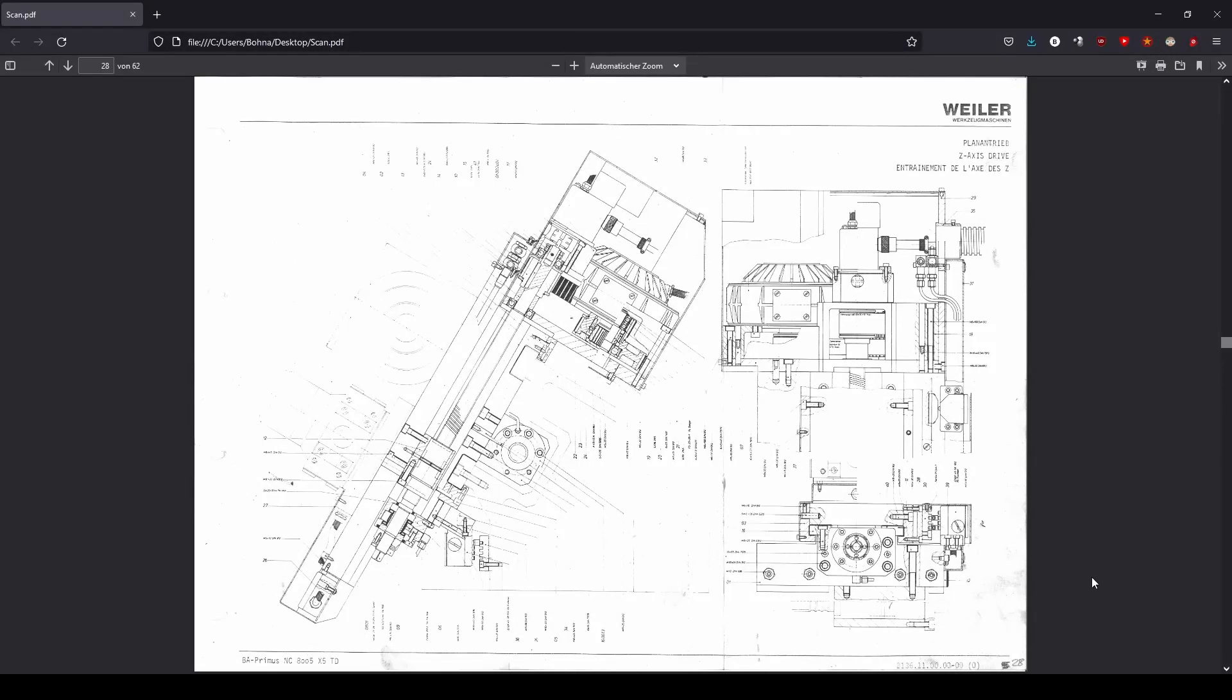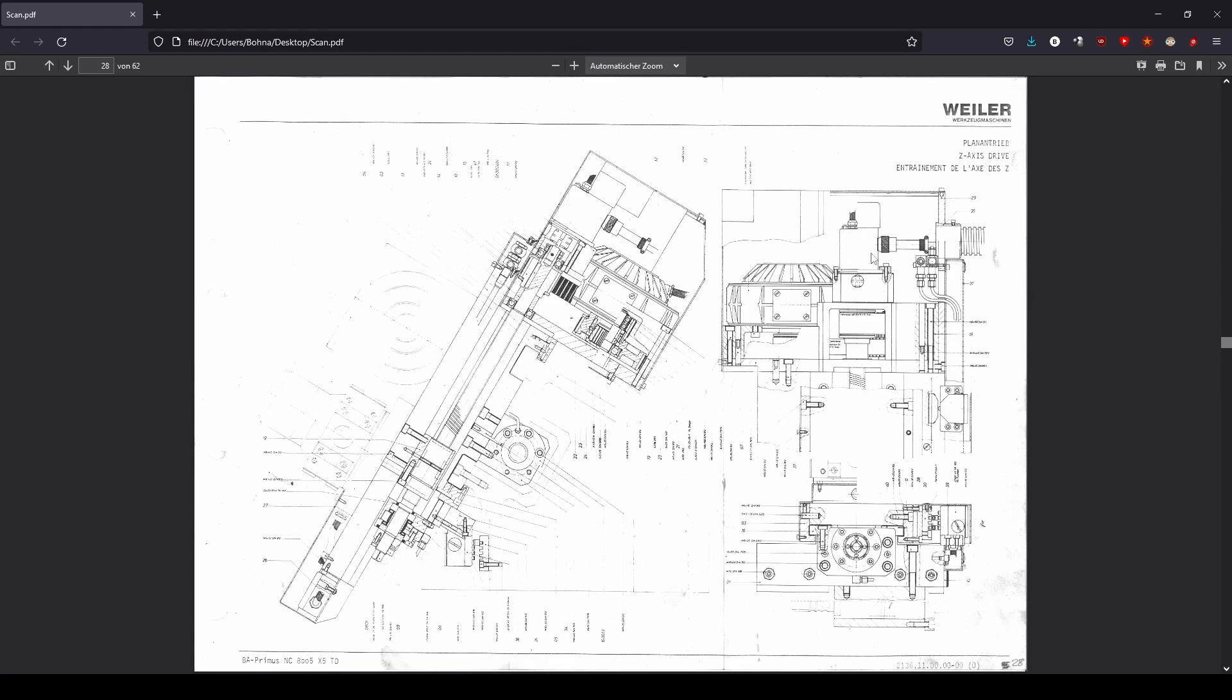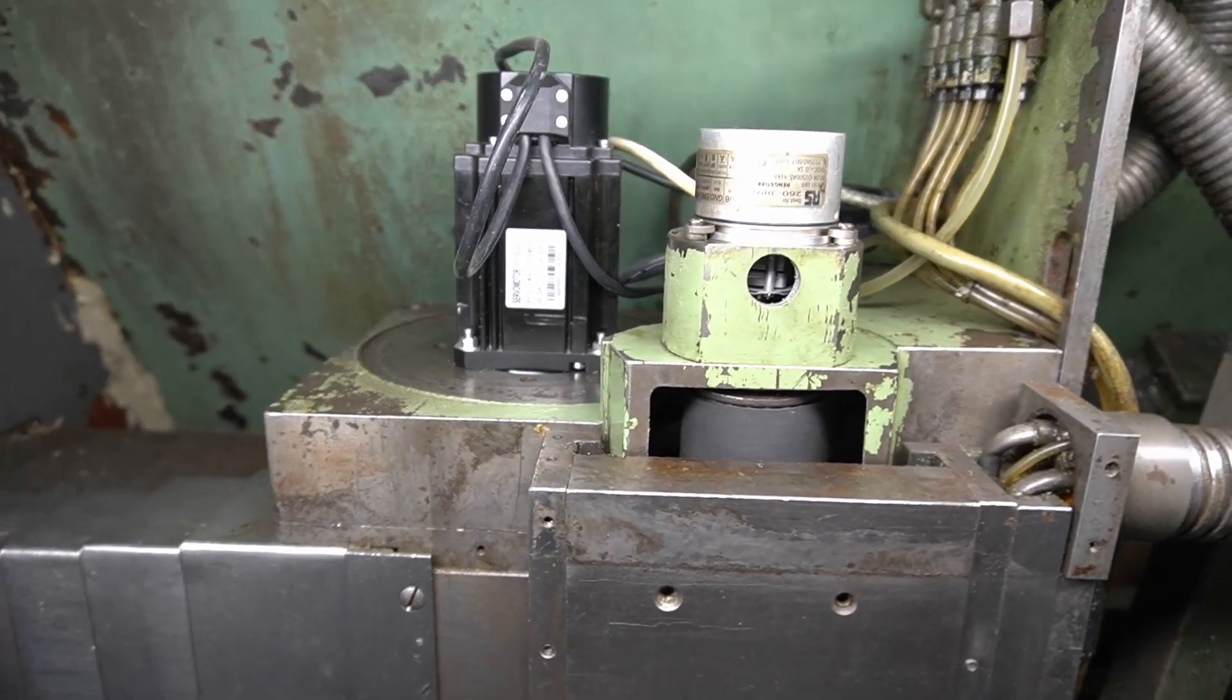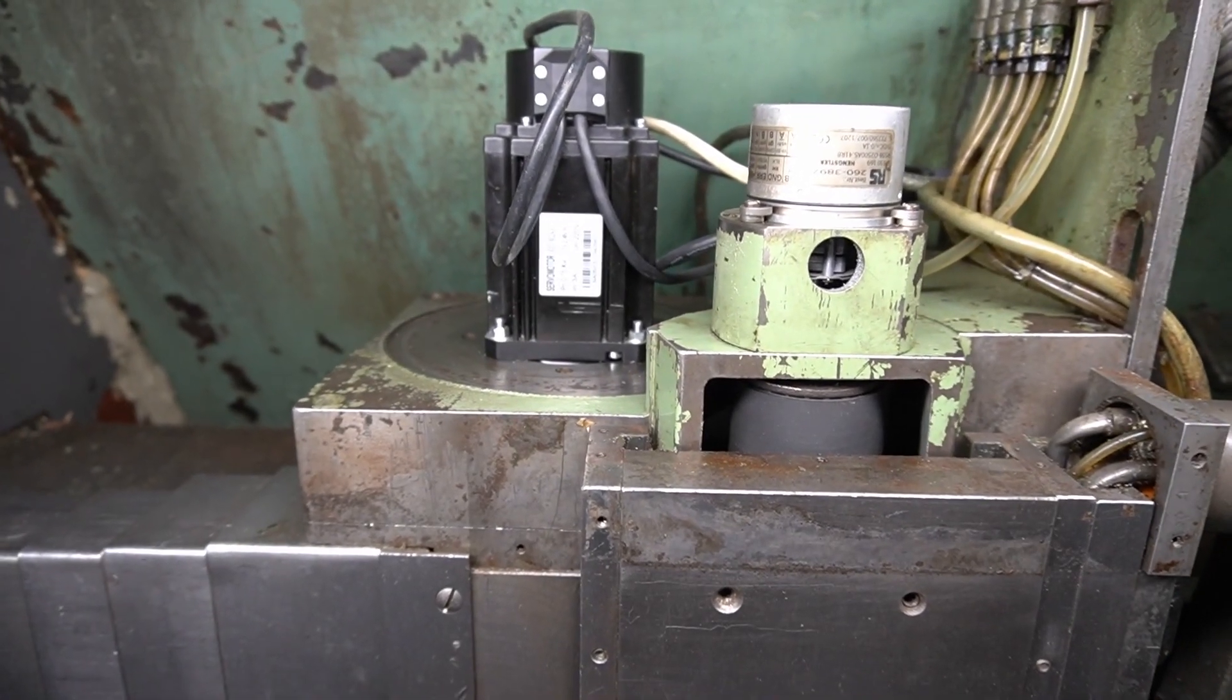Next we see the z-axis drive. The tool turret is shown on the left. You can also see the cover that you see from the outside. At the top of the axis is a box containing the motor for the drive. The motor is driven by two belts as with the x-axis. An encoder is installed on the end of the ball screw. On the right side behind the encoder a couple of lines are drawn. These are distributors of oil lines to lubricate the bearings. All ball bearings and linear guides are supplied with lubricating oil from the central lubrication system. Forks for the oil are drawn in many places in the drawings and you can find them everywhere. So let's have a look at the machine.